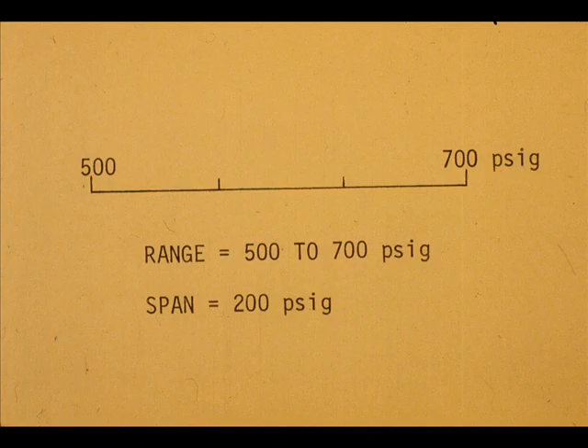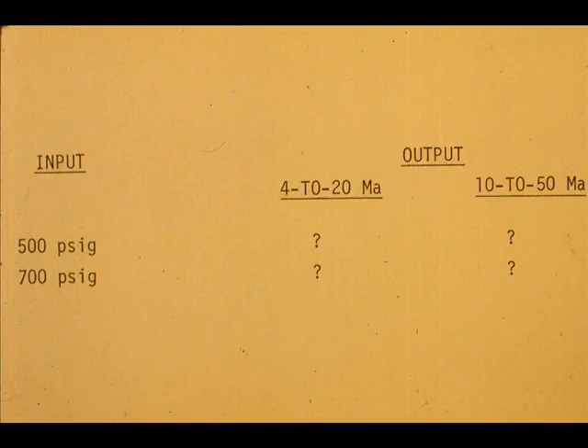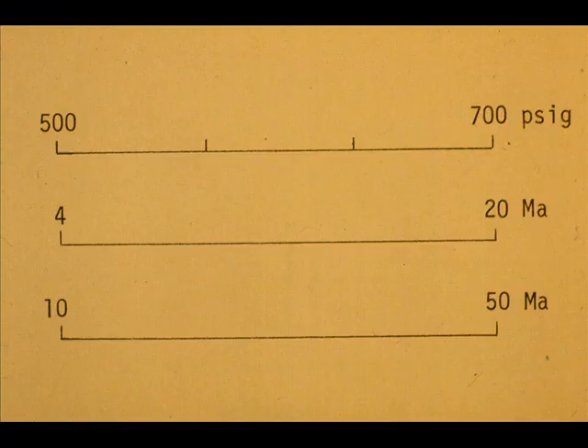Consider if the range of the transmitter is 500 to 700 PSIG instead of 0 to 200 PSIG. The range is different, but the span is still 200 PSIG. At 500 PSI input — the low end of the range — the output should be 4 or 10 milliamps depending on the output range selected. At 700 pounds, the output would be either 20 or 50 milliamps.